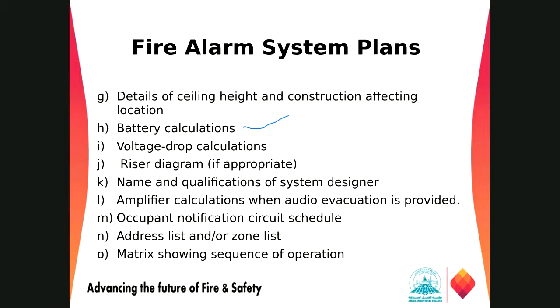You got the point? Yes, I remember it now. So normally, the emergency power supply is required to have sufficient power to operate the fire alarm panel under non-alarm condition. When there is no electrical supply to the building for 24 hours to 60 hours, almost 2 to 3 days, the battery can supply power to those equipment while the alarm system is not activated.